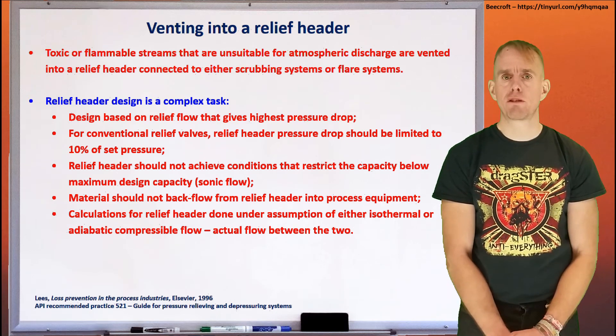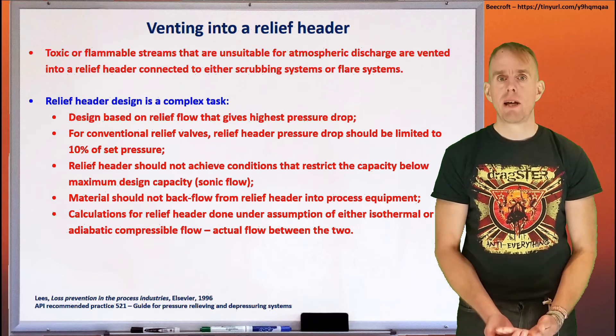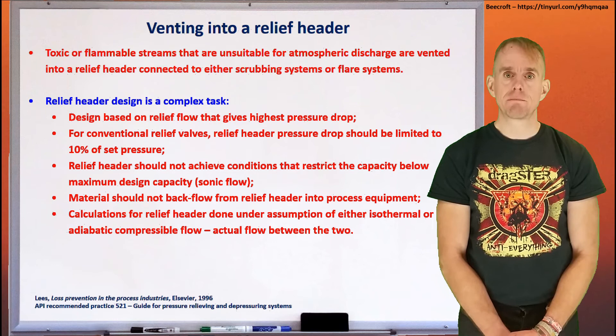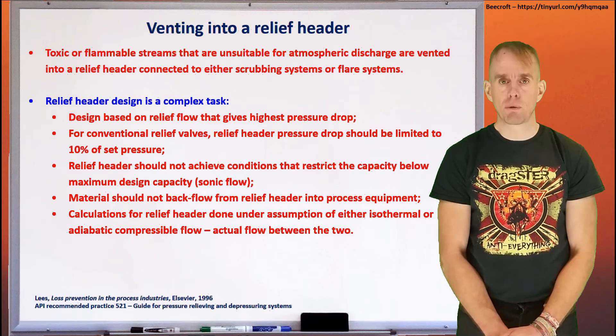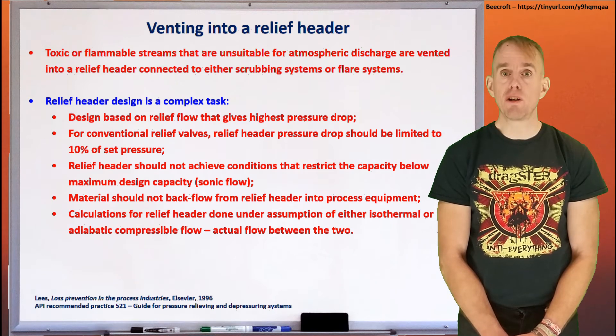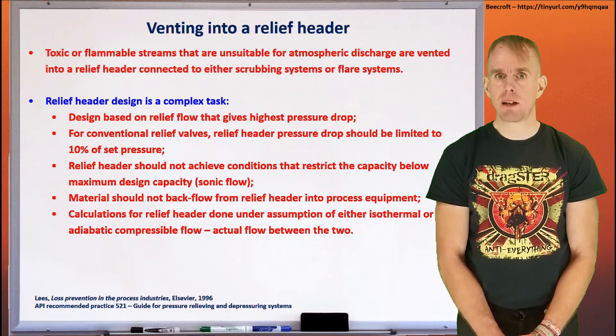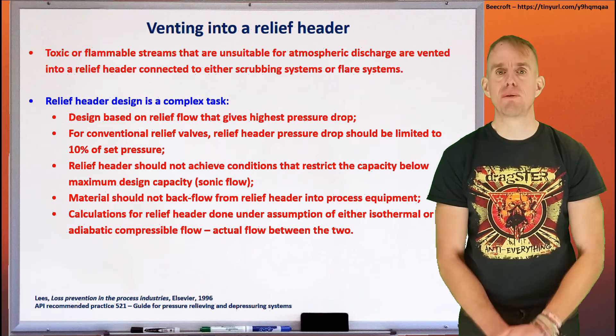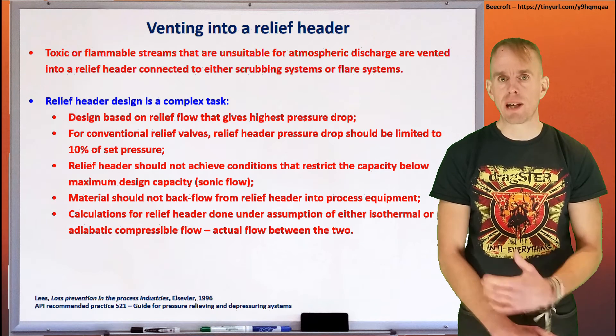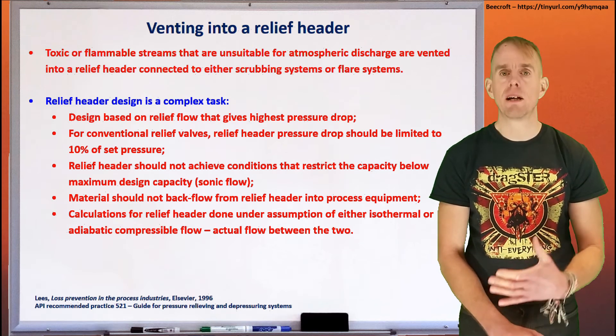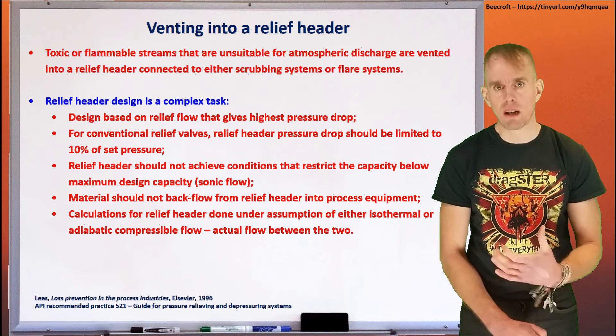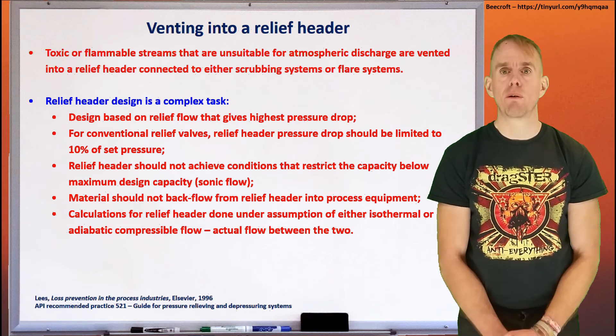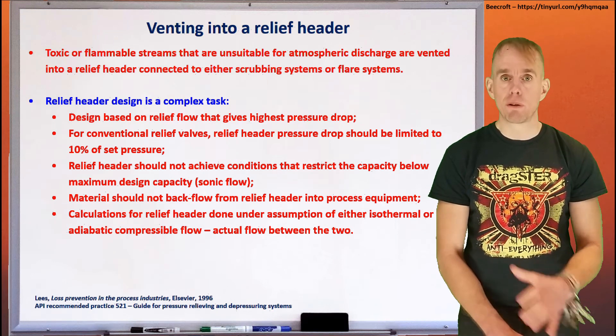When you're designing your relief header, think about pressure segregation. If you have a vessel at high pressure relieving, and that relief header also connects to vessels at low pressure that might be relieving, what happens if that high pressure gas backflows into one of these vessels at a lower pressure? That's what can cause the types of failure that we saw in the last part of this lecture. So for goodness sake, segregate the pressures of the various systems for your relief header.